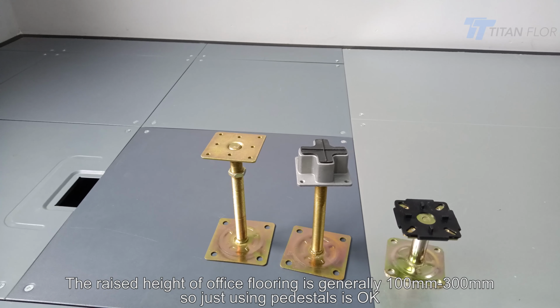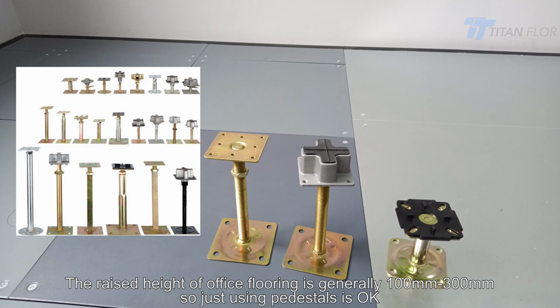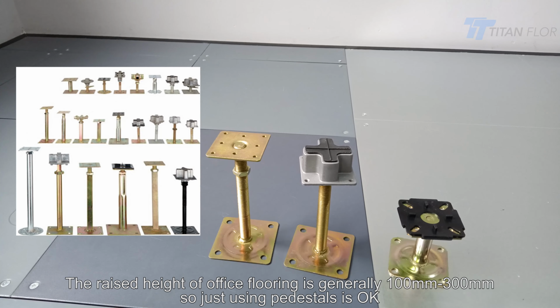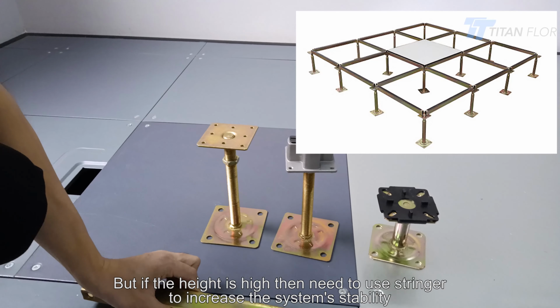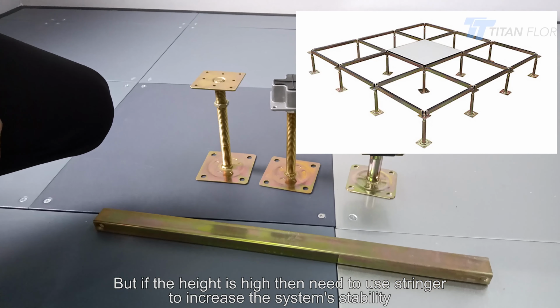The raised height of office flooring is generally 100 to 300 mm, so just using pedestals is okay. But if the height is high, then we need to use stringers to increase the system's stability.